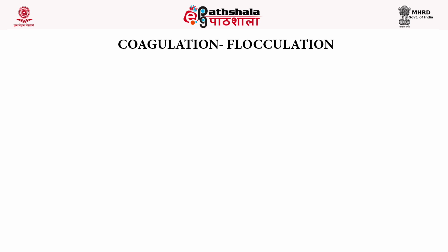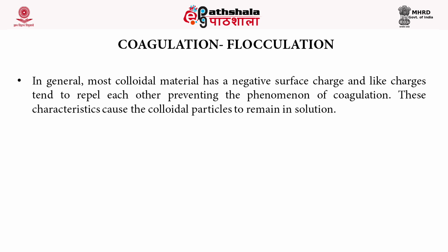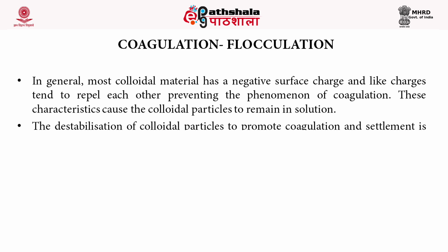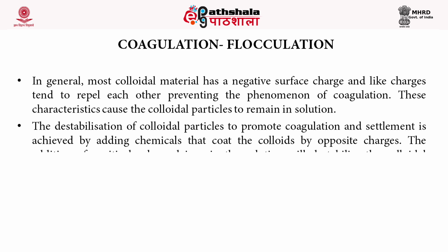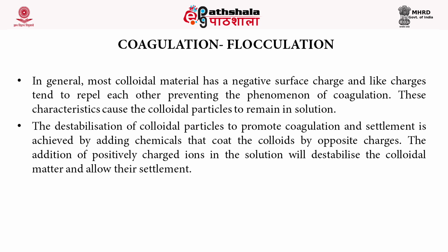In general, most colloidal material has a negative surface charge, and we know very well that like charges tend to repel each other, preventing the phenomenon of coagulation. So these characteristics cause the colloidal particles to remain dispersed in the solution. The destabilization of the colloidal particles to promote their coagulation and settlement is achieved by adding chemicals that coat the colloids with opposite charges. The addition of positively charged ions in the solution will destabilize the colloidal matter and allow their settlement.